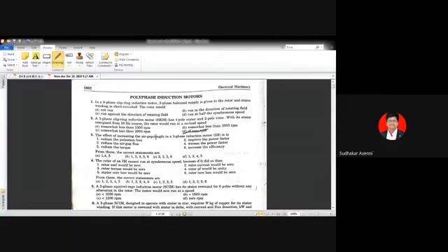When I mu increases, there will automatically be a reduction of power factor. So when I mu increases, the power factor angle increases, and automatically the power factor reduces. That's why option A is the right option. One is the reduction in pulsation losses: when flux is maintained constant, there will be a reduction of losses, that is the pulsation losses. And the power factor is worse. The power factor reduces, then the torque reduces because of increasing the air gap between the rotor and stator.